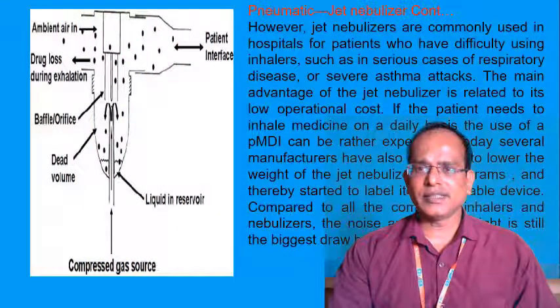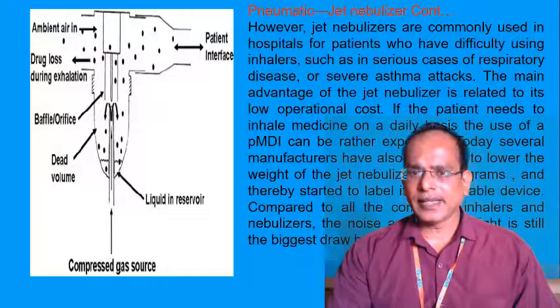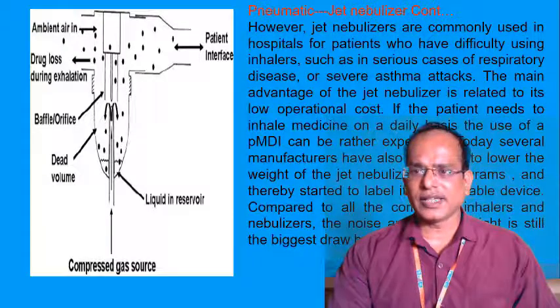However, jet nebulizers are commonly used in hospitals for patients who have difficulty using an inhaler, such as in serious cases of respiratory disease or a severe asthma attack. Those patients can also use the pneumatic jet nebulizer. The main advantage of the jet nebulizer is its low operational cost. If the patient needs to inhale medicine on a daily basis, the use of a pMDI can be rather expensive.